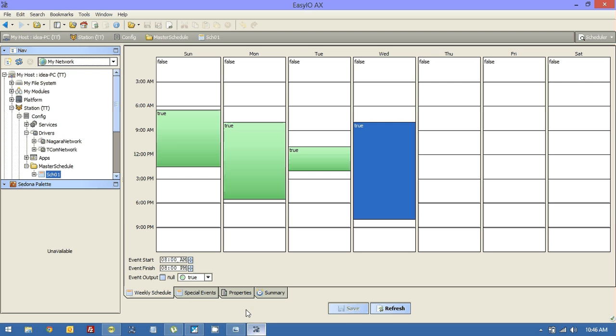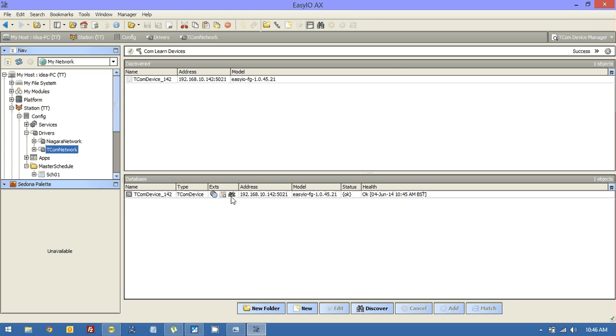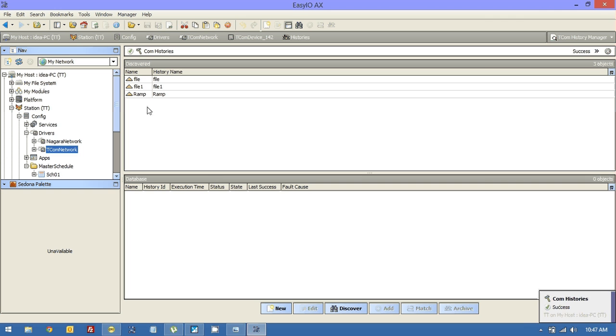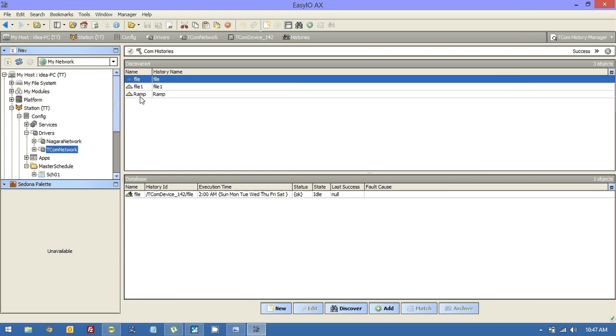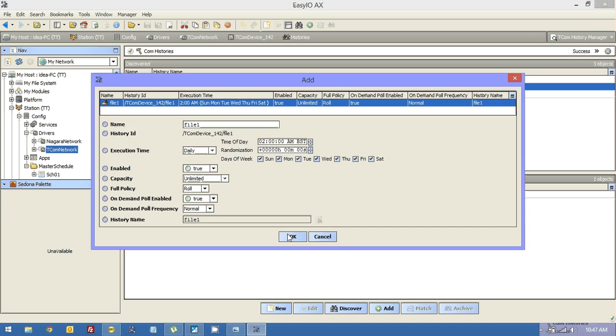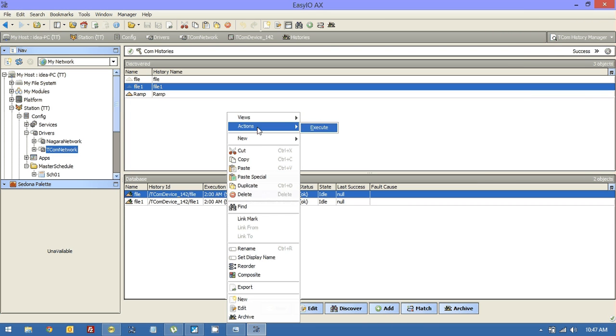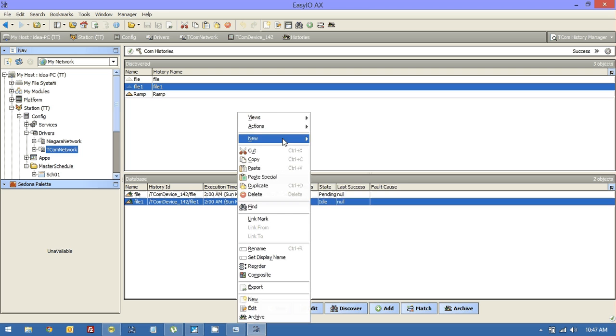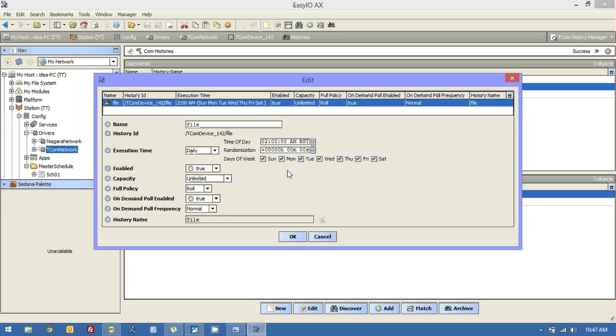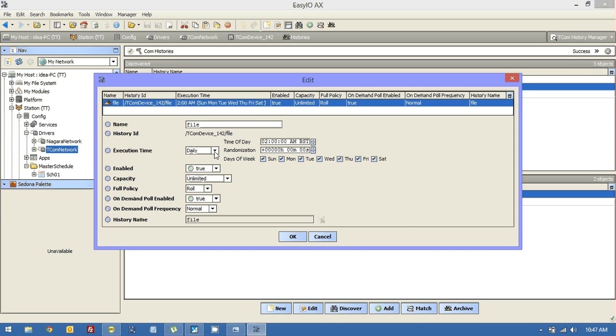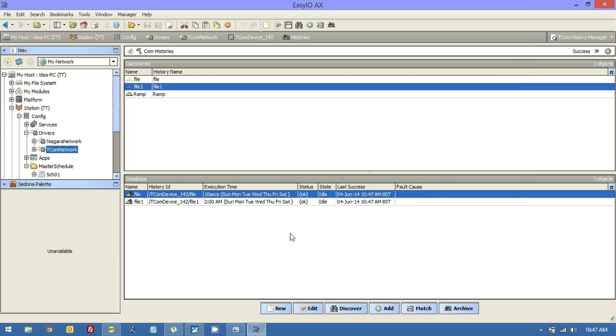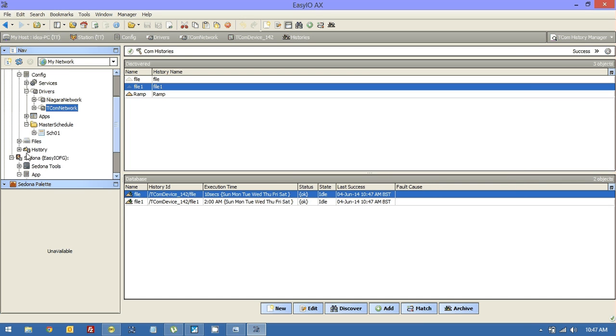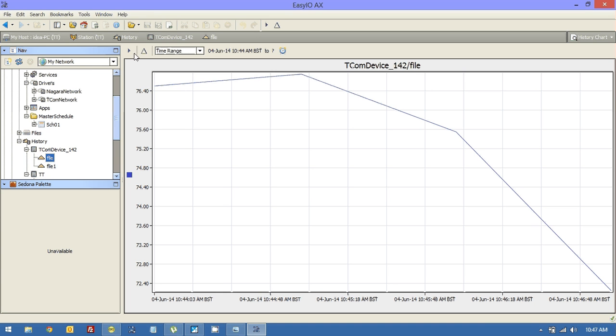The next one is to go to our TCOM network and this time discover histories. And you can see we created those two there. Again, just bring those in. And just to save time, I'll just execute them to create them. Again, we could do the same thing and just put in a really fast update in there to make that interval. So that's a 10 seconds for this. I'll just do one of them for now. The one that's called file. If you go down to here now, you will see that we have histories. We have one called TT, the device. Sorry, I beg your pardon, it should be this one. If I go to file and did a live update, you would see we get new histories now coming straight into Niagara.